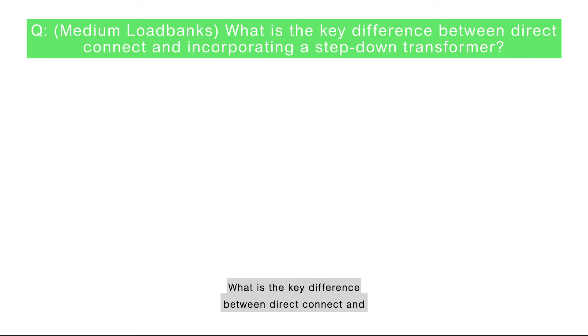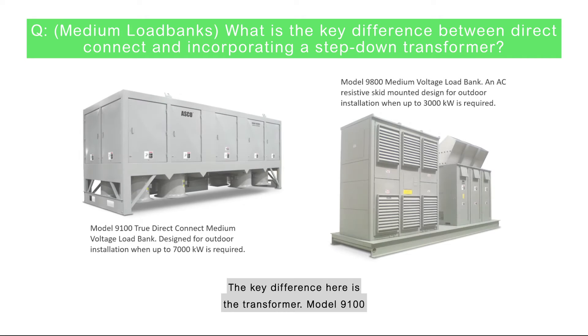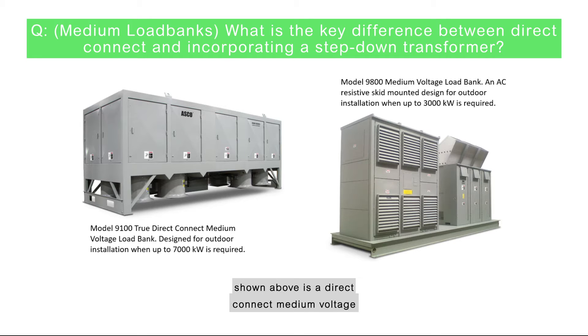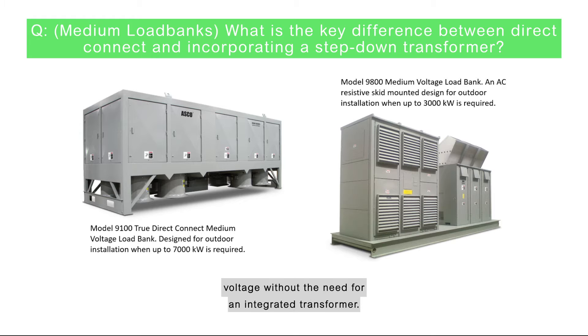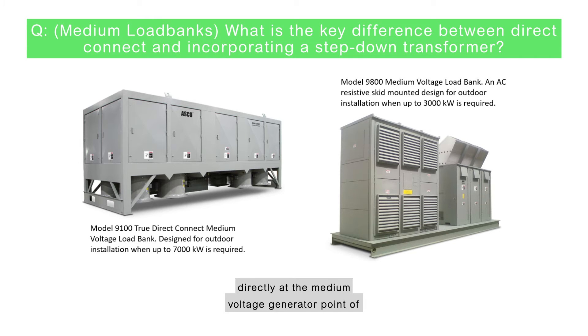What is the key difference between direct connect and incorporating a step-down transformer? The key difference is the transformer. The model 9100 shown above is a direct connect medium voltage load bank. This type of load bank operates at higher voltage without the need for an integrated transformer — the customer can connect the load bank directly at the medium voltage generator point of connection.